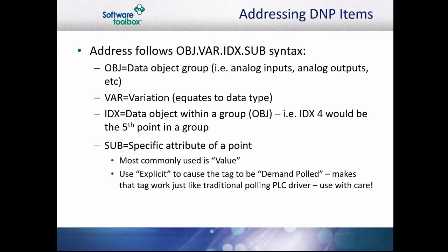But depending on the object and variation, there are a number of attributes available such as dot timestamp, dot explicit, and dot restart. Alternative to dot value, you would use the dot explicit subattribute to cause the tag to become demand polled, which as we discussed earlier will cause the tag to work like tags in traditional polling PLC drivers.